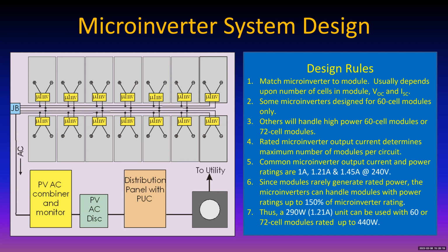The rated microinverter output. A 290 watt microinverter will only put out 1.21 amps, and that's it. No matter what, if the module wants it to do more than that because it's putting out more power, the microinverter says, sorry, I'm current limited. I stop at 1.21, that's it. Of course, that's really nice as far as designing the overcurrent protection.